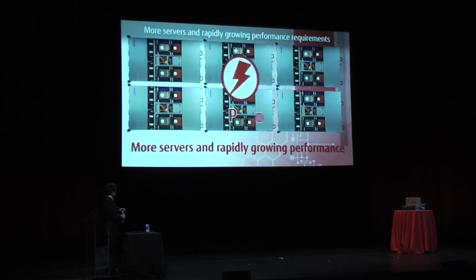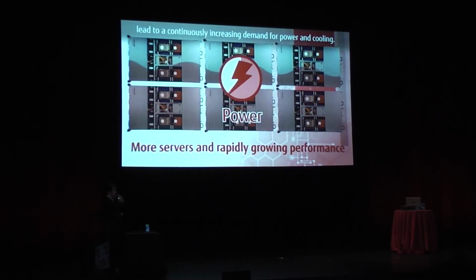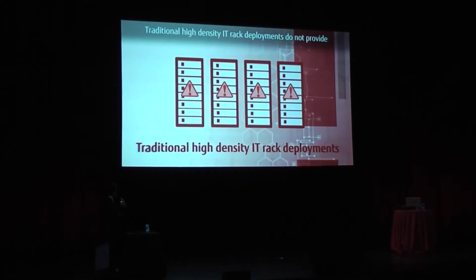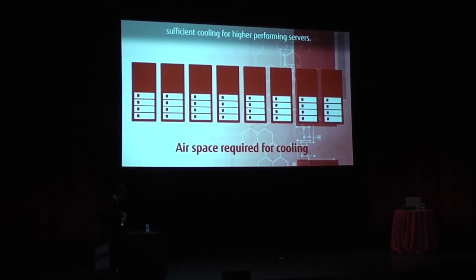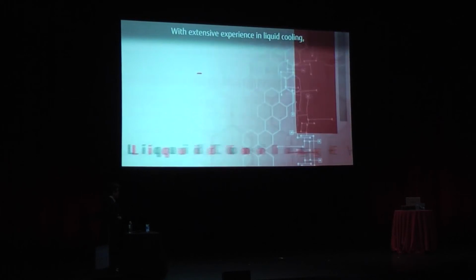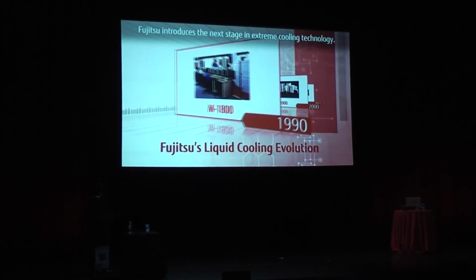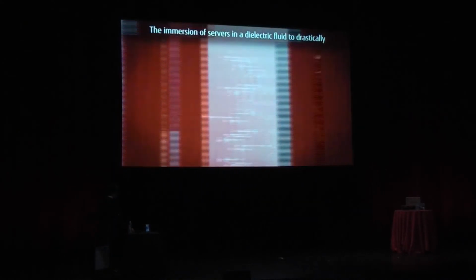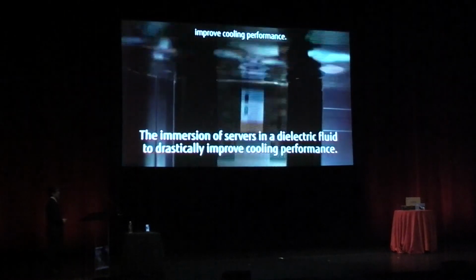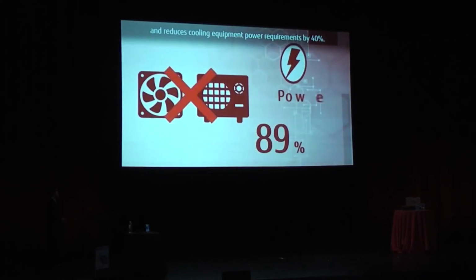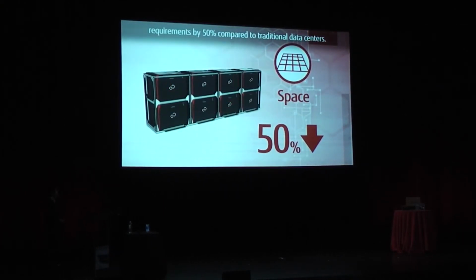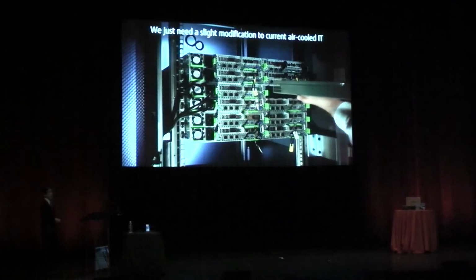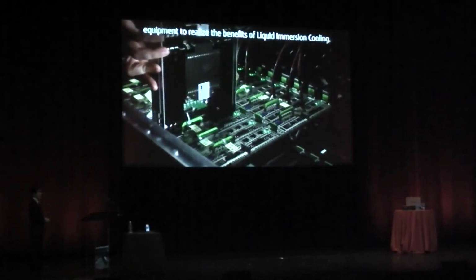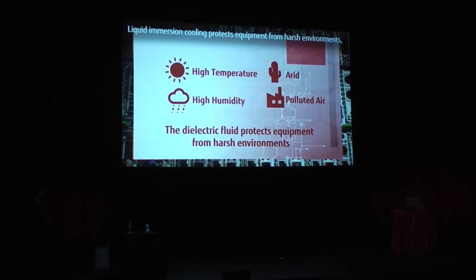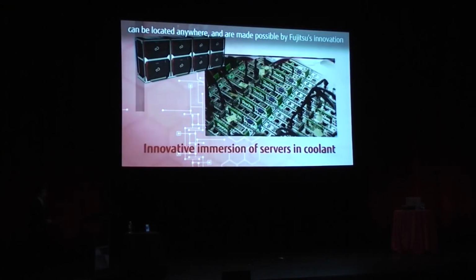More servers and rapidly growing performance requirements lead to a continuously increasing demand for power and cooling. Traditional high-density IT rack deployments do not provide sufficient cooling for higher-performing servers. The Fujitsu Liquid Immersion Cooling System: with extensive experience in liquid cooling, Fujitsu introduces the next stage in extreme cooling technology - the immersion of servers in a dielectric fluid to drastically improve cooling performance, reducing cooling equipment power requirements by 40% and decreasing floor space requirements by 50% compared to traditional data centers. We just need a slight modification to current air-cooled IT equipment to realize the benefits of liquid immersion cooling, which protects equipment from harsh environments and is made possible by Fujitsu's innovation.